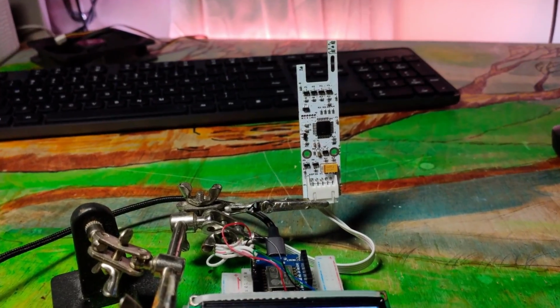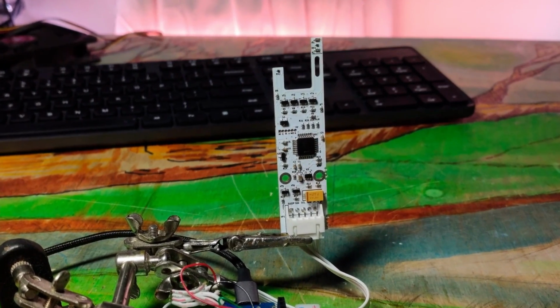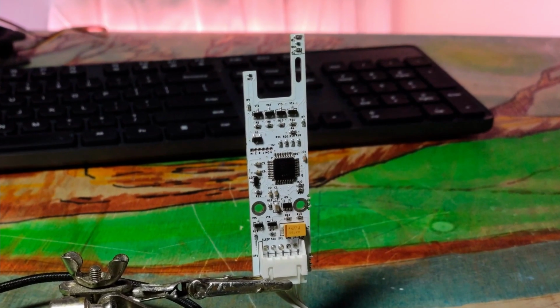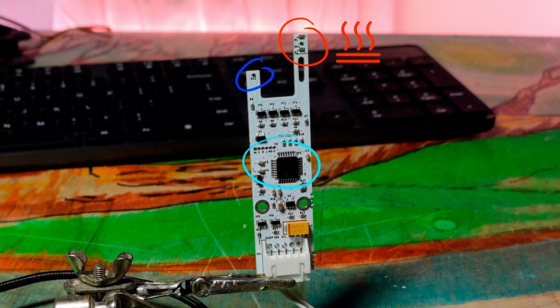In general, a thermal anemometer doesn't have any moving parts. One of the sensors is heated up to a certain constant temperature, and the second sensor measures the temperature of the airflow. Based on the heater power dissipation required to maintain the temperature of the first sensor, the controller calculates the airflow rate.